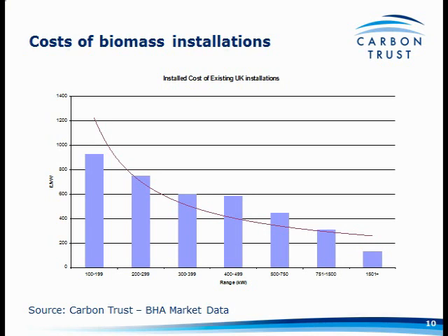I put together a tool that tries to calculate — or give you an idea of — the capital costs of a biomass system of various different sizes. I based it on this curve but added about 20% to that cost for increased complexity and rising technology costs. As you can see, further down this end — where a lot of the bigger nurseries will be, at one and a half megawatts-plus — that's going to be around £120 per kilowatt, compared to an oil or gas boiler at roughly £50 per kilowatt. So at least twice, if not three times the cost. And the smaller you get, the more expensive it becomes in terms of cost per kilowatt.